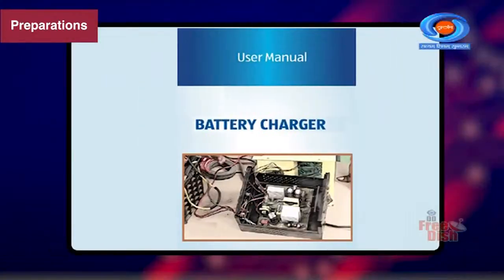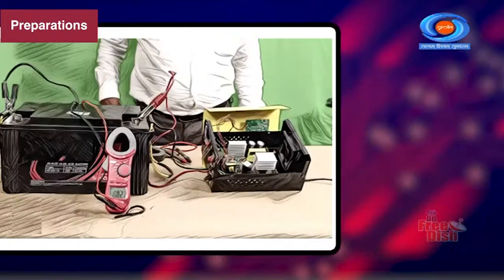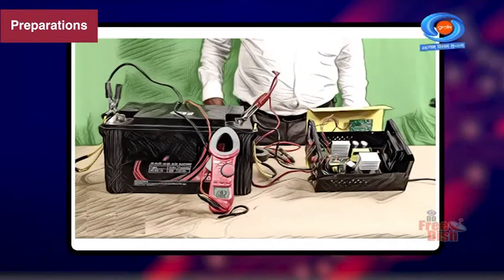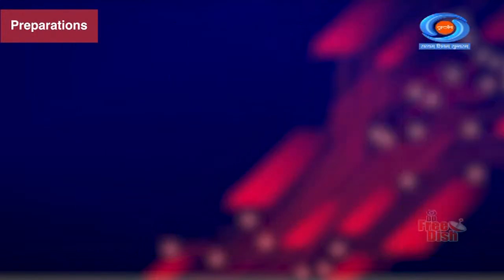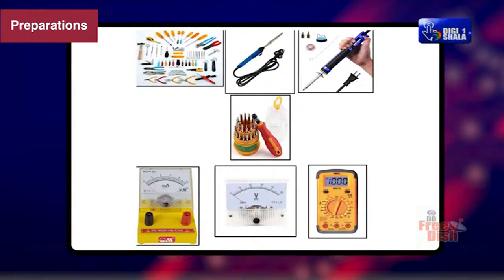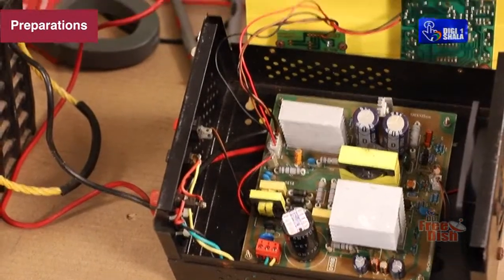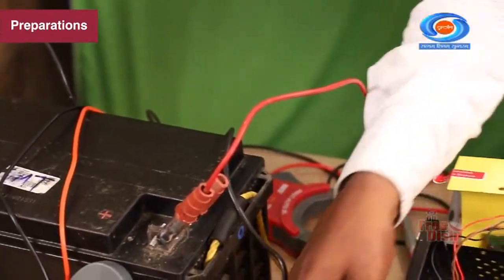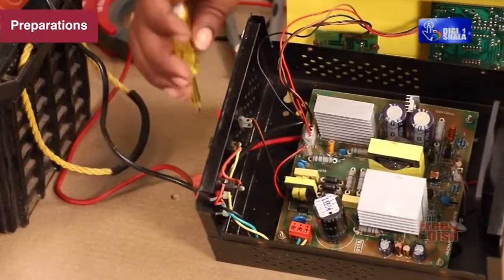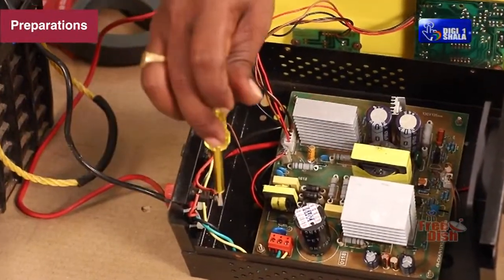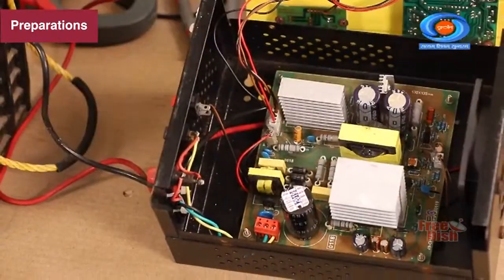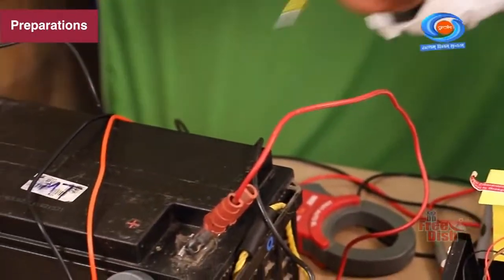Familiarize yourself with the charger's user manual. It will provide specific instructions on operation, troubleshooting and safety precautions for that particular model. Gain a good understanding of how the charger works, including its components, voltage ratings and charging algorithms. This will help you troubleshoot any issues that may arise. Collect the necessary tools and equipment for servicing and troubleshooting. Examine the battery charger for any visible signs of damage or loose connections. Check the power cord, input and output terminals, control knobs and display for any issues. If you notice any physical damage, note down the repairing.